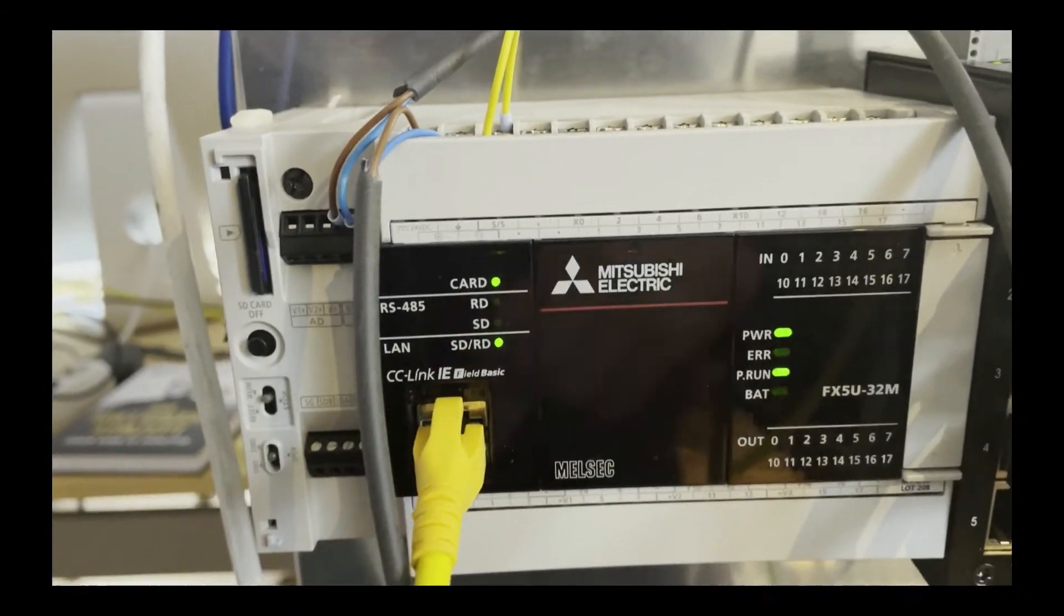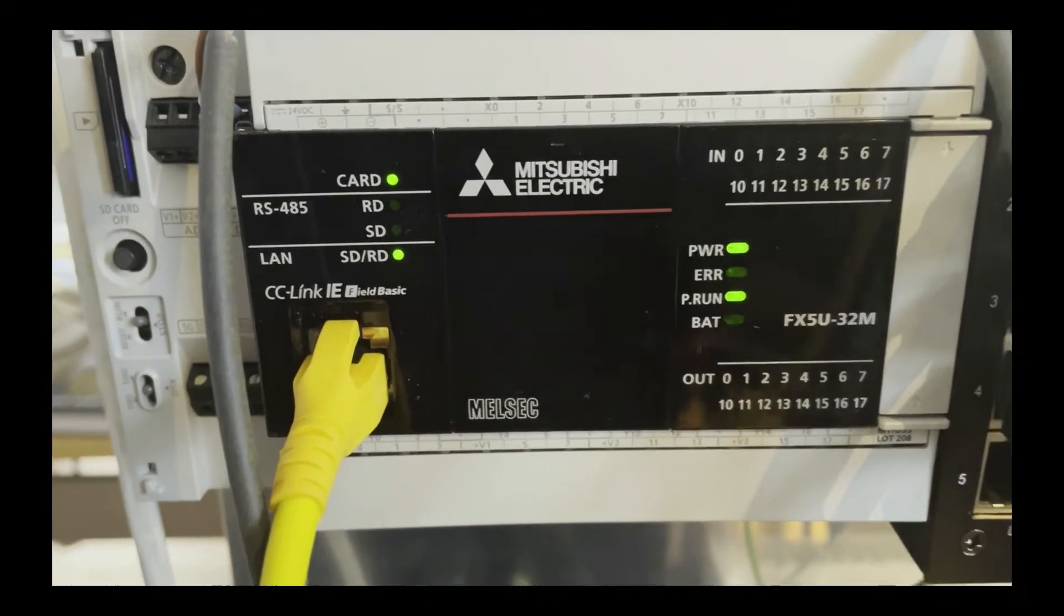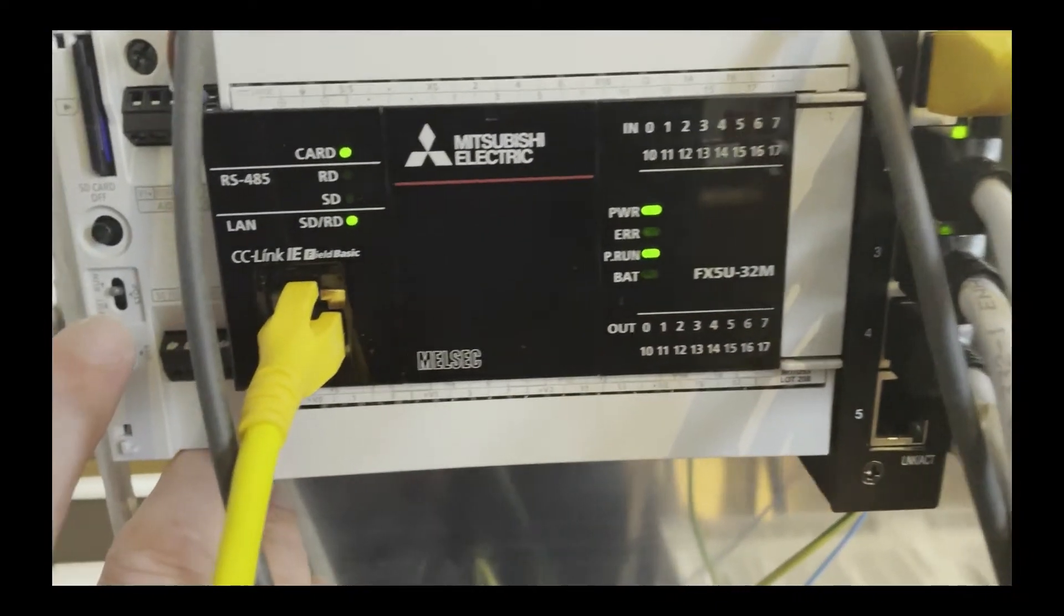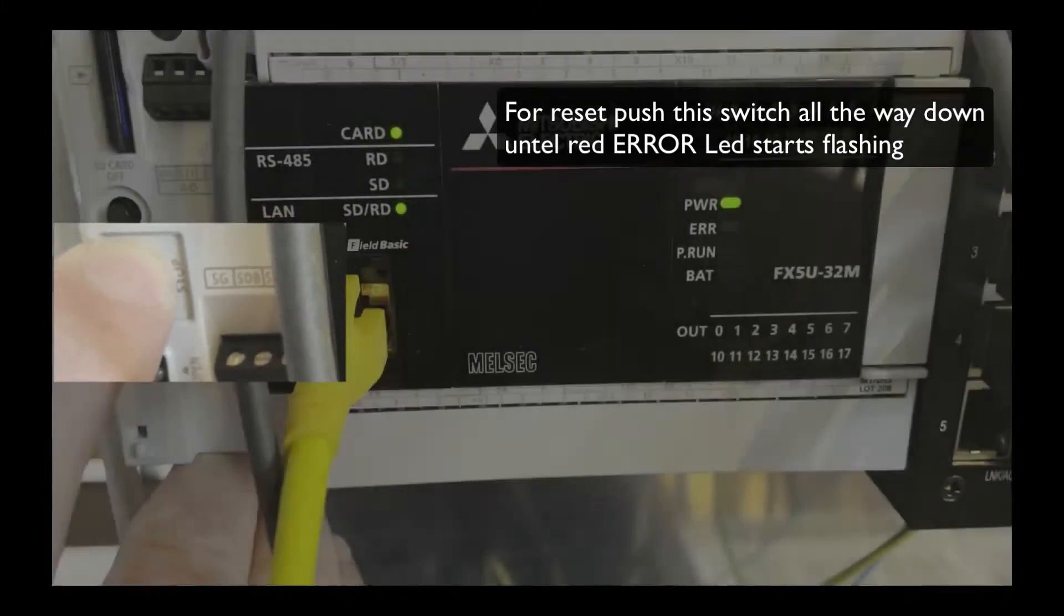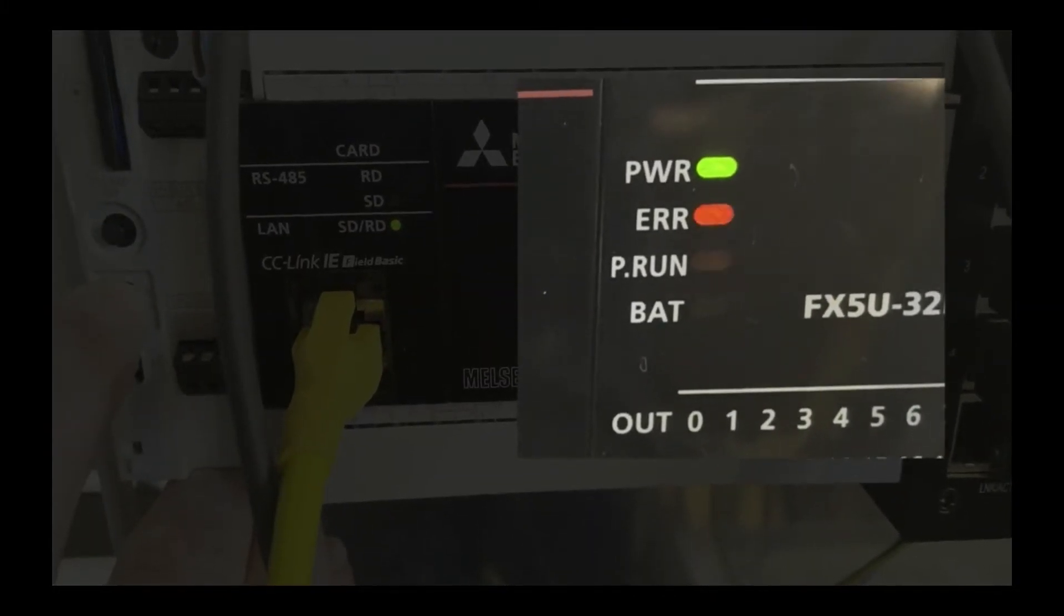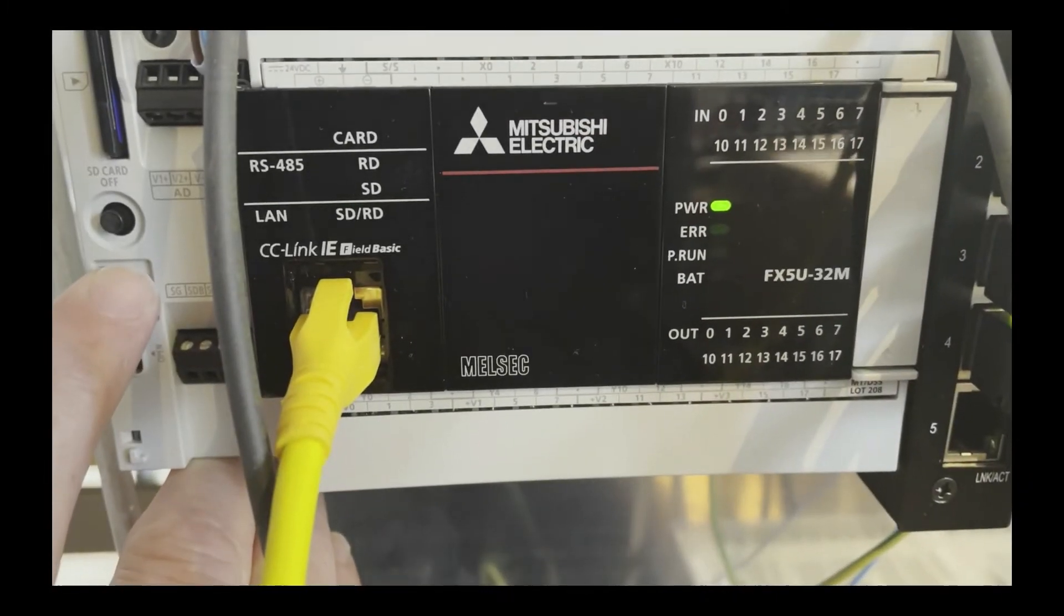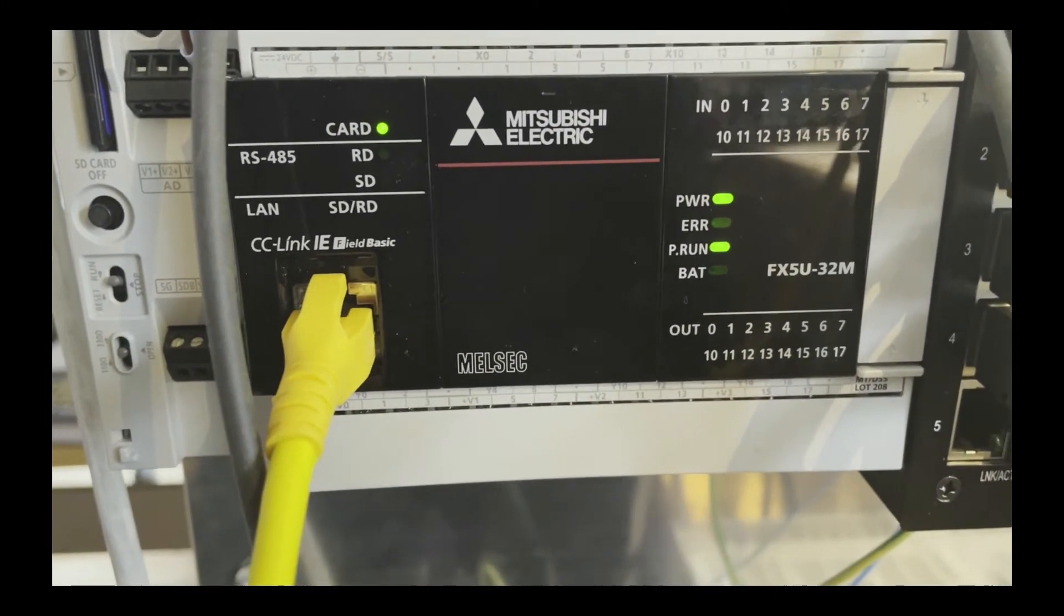Under this lid you find a switch for the operation mode. If you push this all the way down until the red error LED starts flashing and then release the button back to run, your FX5U CPU is reset.